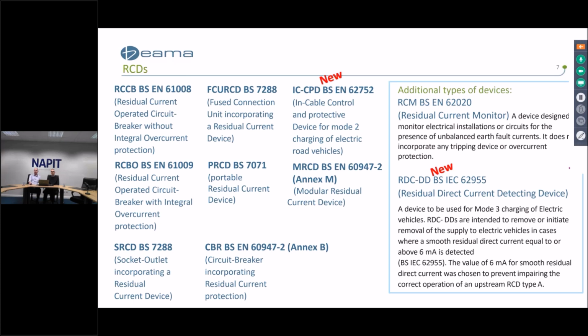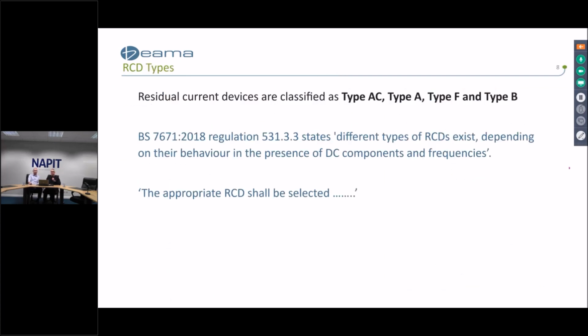Again, not an RCD. It doesn't open the circuit when it detects a residual current, but it just provides a monitoring service, either by an indicator or an alarm. And that's covered by BS EN 62020. So you can see there's quite a family of different RCDs to take into account. Okay. One thing I should mention about that previous slide is that Type F and Type B, which we'll come on to, are covered by another product standard, which is BS EN 62423, and that includes additional requirements on top of the RCCB and the RCBO standards.